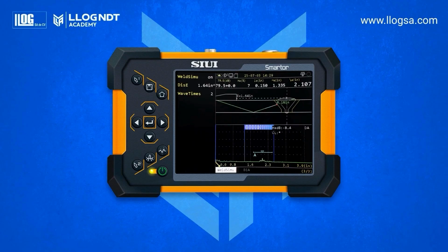When performing an inspection and a discontinuity is detected, enter the surface distance as the E value. With this information, the simulator will display a red indication showing the location of the discontinuity in the weld. As additional information, it is also possible to activate the number of beams in the simulator. We've completed the optimal handling of the Smartor Ultrasonic Flaw Detector.